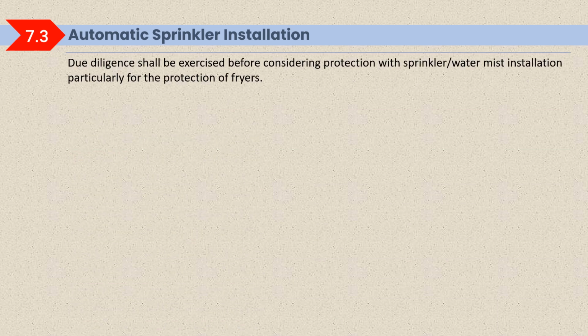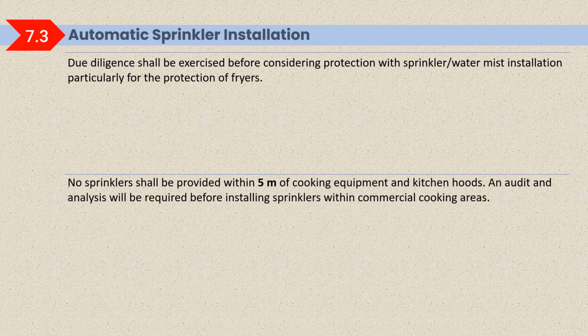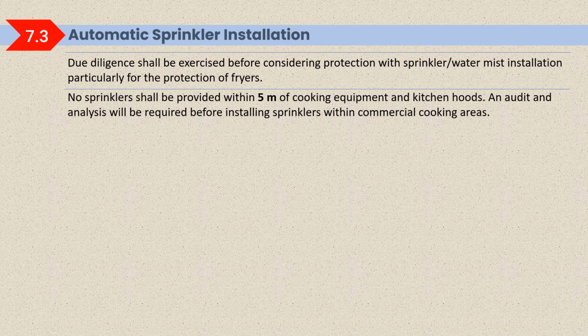Automatic sprinkler installation. Due diligence shall be exercised before considering protection with sprinkler/water mist installation, particularly for protection of fryers. So it needs to be very carefully studied before providing the protection of sprinkler or water inside the hood or duct, because if we throw water on fryers it may cause more damage. No sprinkler shall be provided within 5 meters of cooking equipment and kitchen hood. So here it is mentioned within 5 meters there should be no sprinkler.